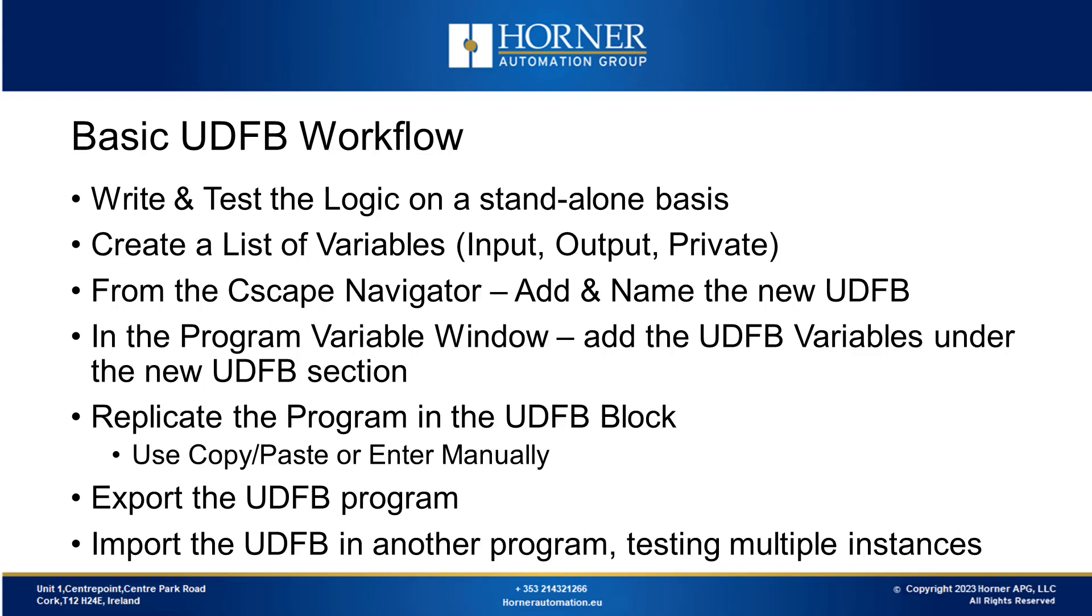The next step is to create a new program in the Cscape Navigator and add a new UDFB giving it an appropriate name. Upon naming it, a new section appears under the UDFB name in the program variable window. Here you can define the required input, output and private variables.